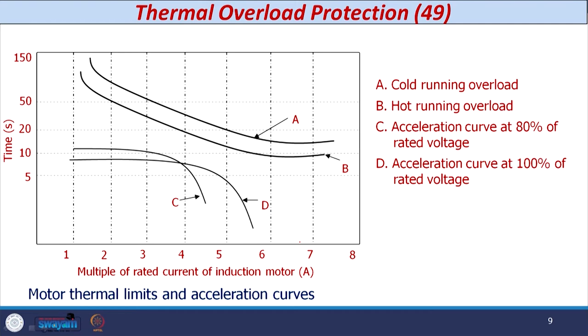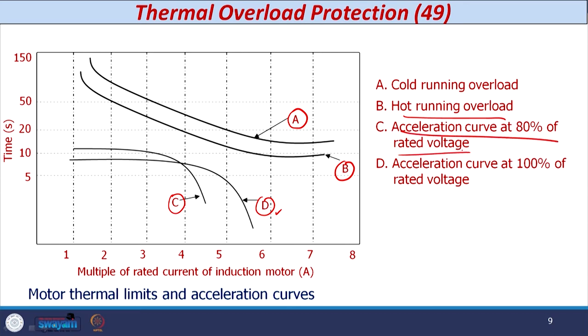Looking at the curve, curve A is provided for when you start the motor during cold condition and it is in running condition with overload. Just below curve A, there is another curve for running the motor in overload condition when it is in hot condition. The other two curves — curve C and curve D — are the acceleration curves: C is at 80 percent of the stator voltage and D is at 100 percent of the rated voltage. When considering relay settings, you need to consider the acceleration curve with 80 percent of the rated voltage.